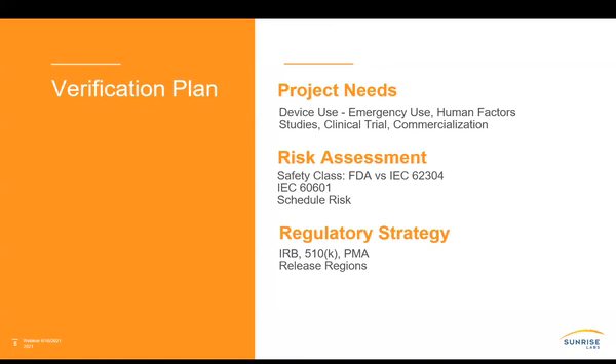And in a lot of cases, I recommend that they are not overlapping, because you can really sort of write yourself into a conundrum if you do that. So in terms of essential performance, that is usually a definition that's given to a national testing laboratory like UL or TUV as part of the 60601 definition.